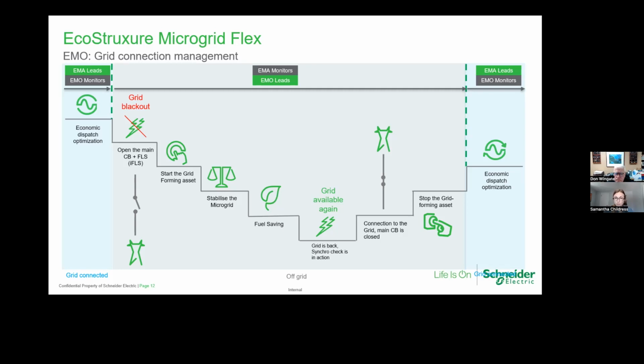When the grid becomes available again, we have what we call an open transition, meaning there's a momentary outage to go back to the grid. This is a short duration outage, often not very noticeable from a facilities perspective. You turn off your generator and solar battery, connect back into the utility system, and stop the grid forming assets. Then you're back in grid connected mode, optimizing your site based on the financial and economic characteristics you're trying to achieve.